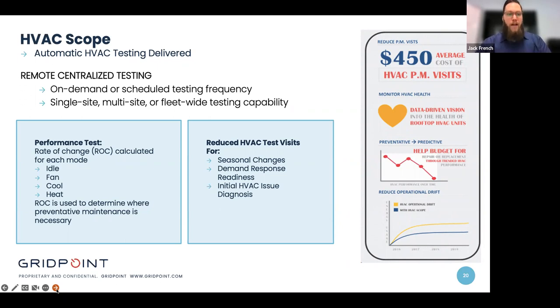So we have a performance test, which basically calculates a rate of change for each mode. We start the unit out in idle mode, we purge the duct, and then we allow the fan to run, we take measurements, and then we allow cooling to happen, we take measurements, we allow heating to happen, we take measurements. So we're basically wanting to see how far the supply temperature and the zone temperature were influenced during this test. And it's a very brief test. We usually run these during the unoccupied hours, so this does not interfere with normal business operations.